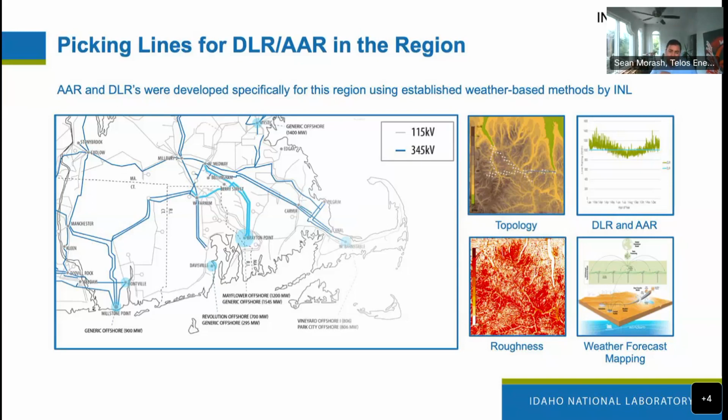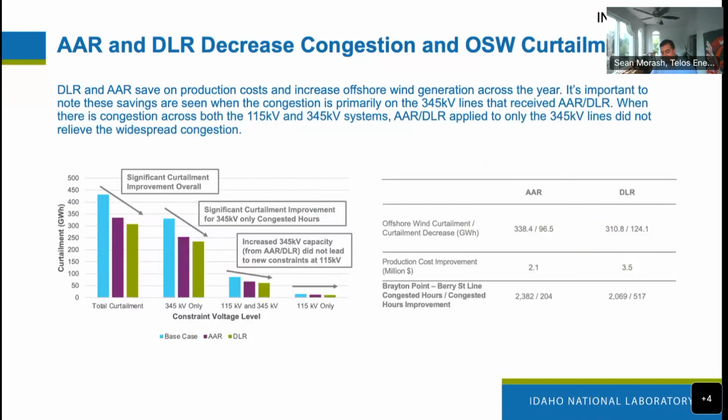We could get into how we calculate those DLRs. Jake can go for the whole rest of our session on how that's calculated. Anyway, we've got a profile of DLRs. We feed that in, and we've adjusted our constraints based on our new line limits, right? And so we're able to say, okay, man, we're able to go from like 430, something like that, gigawatt hours of system curtailment down like 100 gigawatt hours, down 100 gigawatt hours.